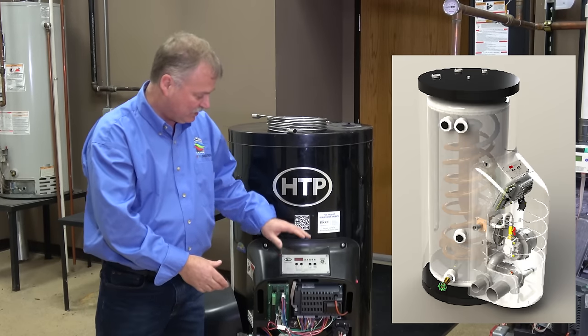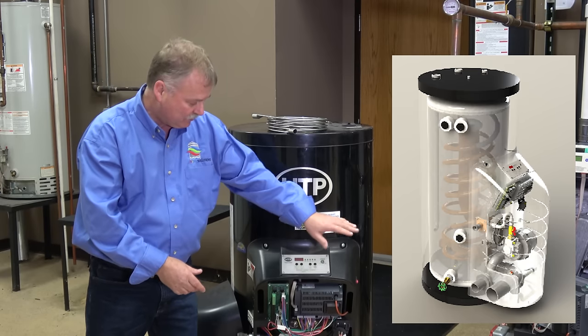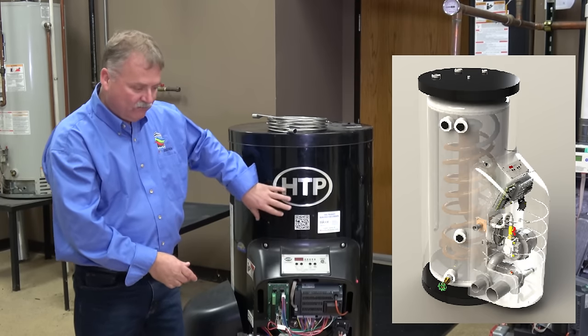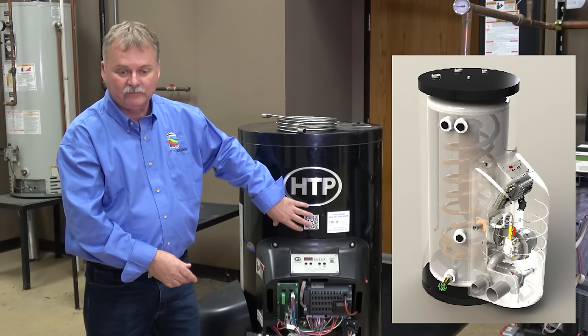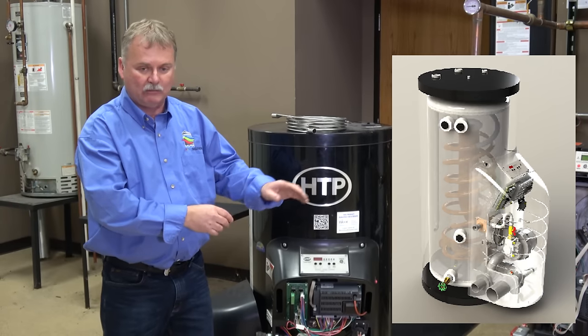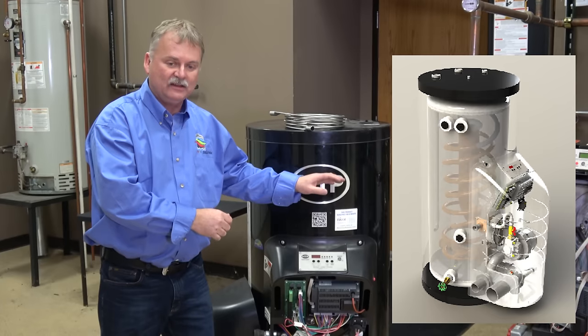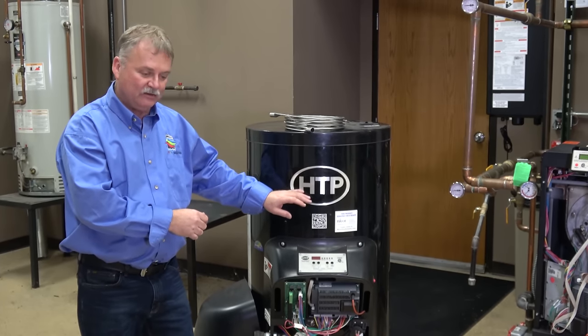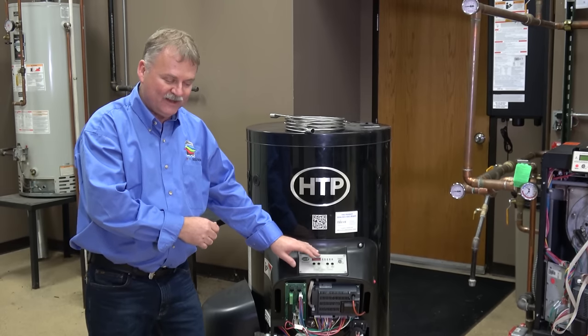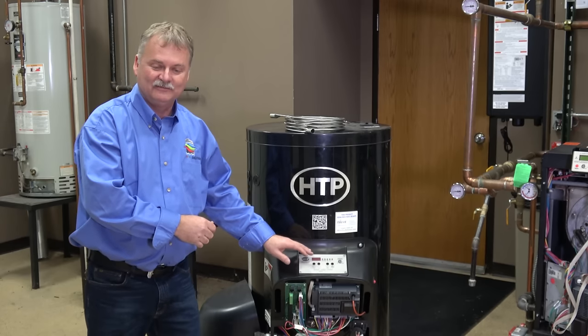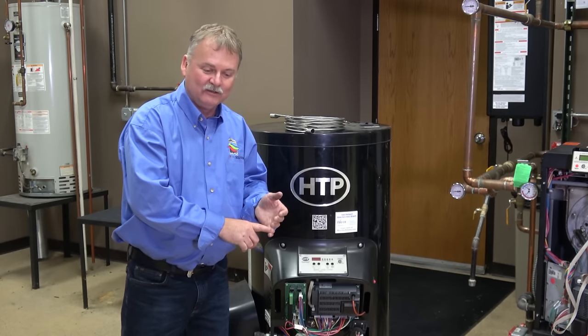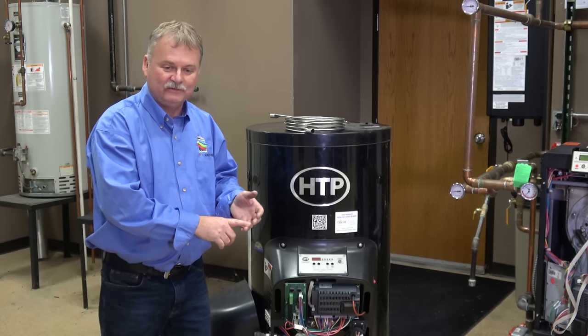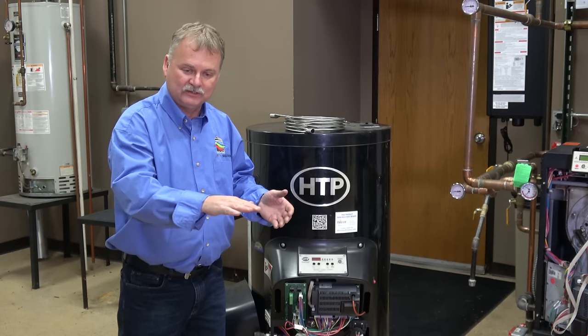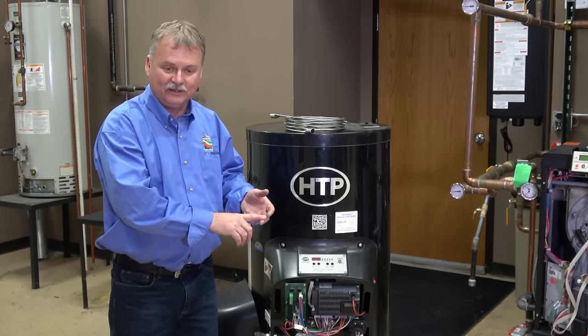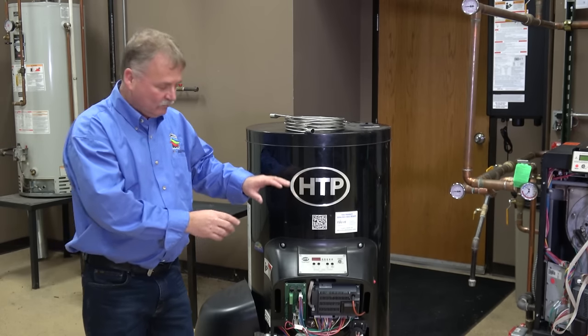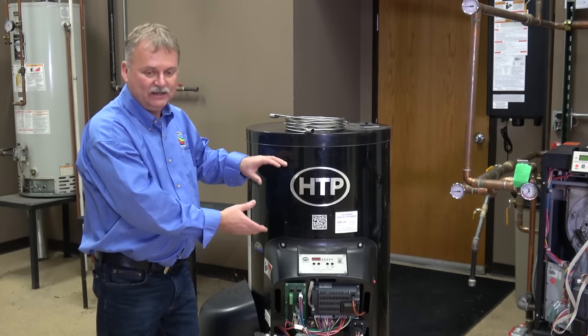So what happens in this, we get a call for heat, the computer, same computer system, looks at it, decides what temperature it should be, and fills up this tank with that temperature water. So now, as our zones are calling or our apartments are calling, we pull BTUs out of this tank. And until we cool these 55 gallons of BTUs down enough, we don't fire the burner. What does that do for us? Well, remember earlier we discussed the most efficient boiler is one that's off. The second most efficient boiler is one that's running at a steady state. Just sit there cruising along. The third and the worst is cycling. This eliminates cycling.